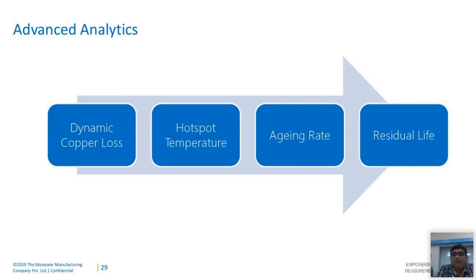Now, when we touch upon the aging of the transformer, it is essential to understand there are different technologies or methods in which the aging of the transformer can be evaluated. Fundamentally, we are using the thermal model for understanding the aging rate of the transformer. Based on the monitored parameters, using the thermal model, we estimate the hotspot temperature, and based on the design type, ratings of the transformer, and the type of paper insulation and type of oil used, we monitor the hotspot temperature continuously.